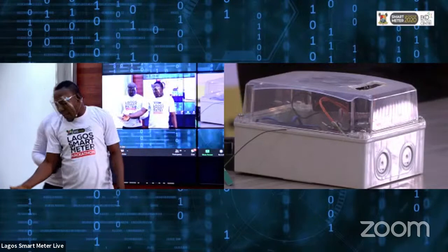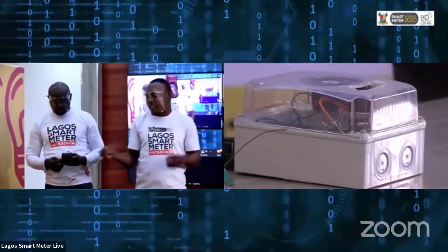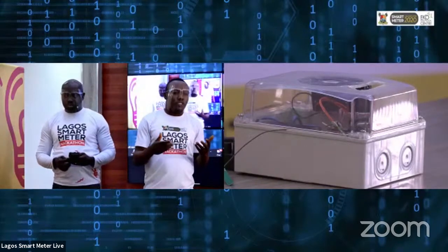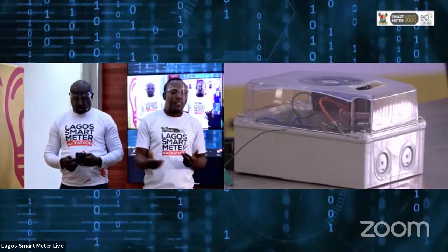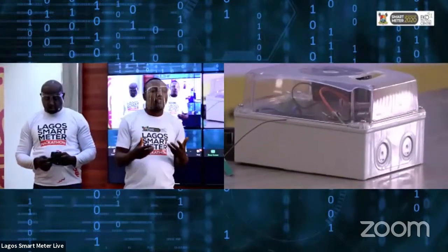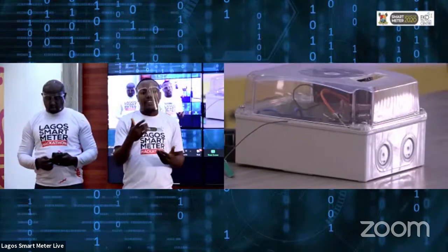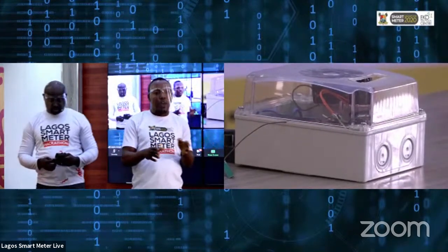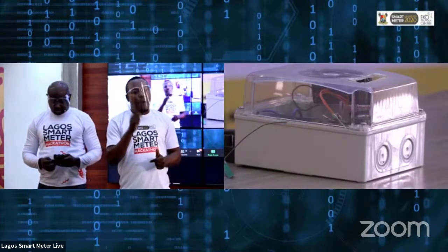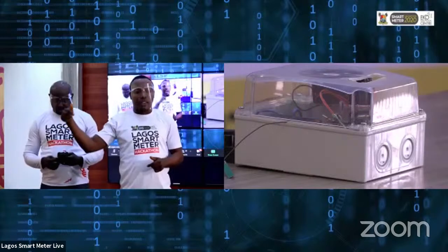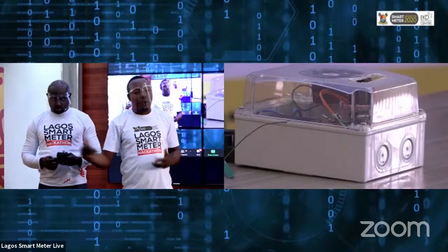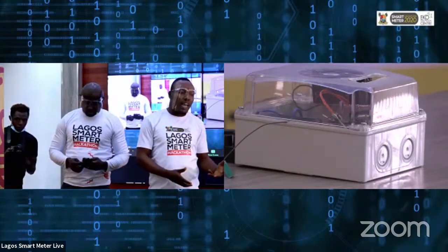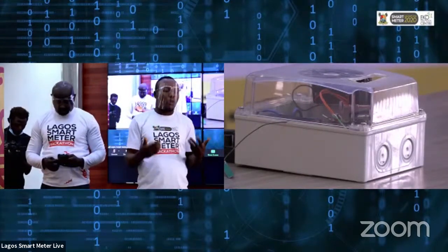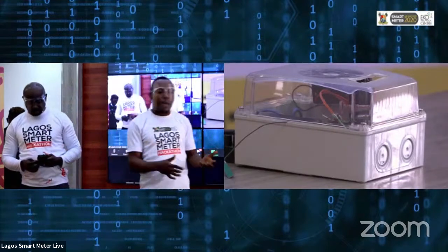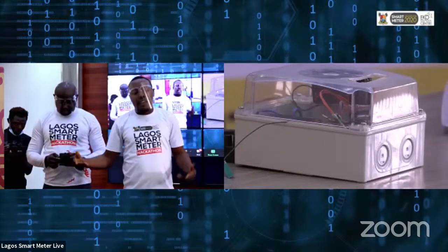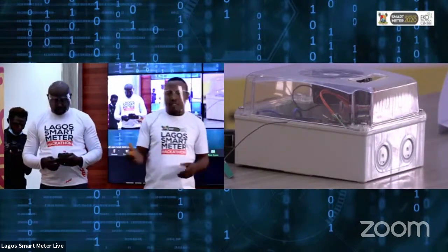One of the other features of this meter is that it is bidirectional. It monitors energy using a bidirectional current sensor, which can also be used to sense bypass. If there's a bypass of the live line but the neutral is still somehow connected to the meter, it will sense current in the neutral line with no energy flow actually recorded in the meter. This will trigger the controller that there might be a bypass. It may not actually be a bypass, but it's worth checking, apart from the tamper switch.